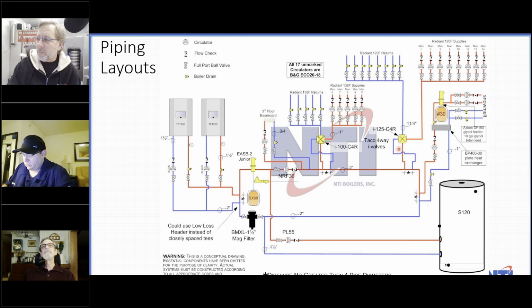Then I came around, and I should have probably taken this off earlier, but I was more concerned about the cold return, which is why I brought that up about the cold return for you, Ted, because you really solved that problem. But here I have a plate heat exchanger going off to 2 closely spaced T's, again with a circulator, like they all have circulators, going to the plate heat exchanger. My glycol pump comes into here, off it goes for the 2 radiant zones, and then back again to the system. That was one that I solved the problem out in Michigan with.